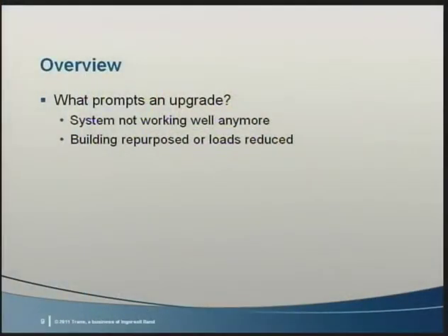Now, the discussion for upgrading a chilled water plant begins for a number of reasons. One is that the system's not working well anymore, or the building's purpose may have changed. Energy management reduced the lights and the building construction was improved, or it may be that the building is simply no longer operating efficiently.